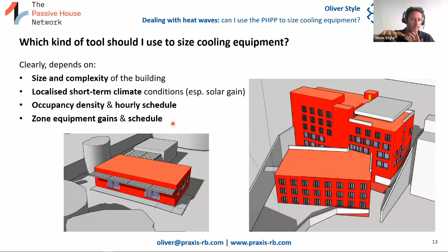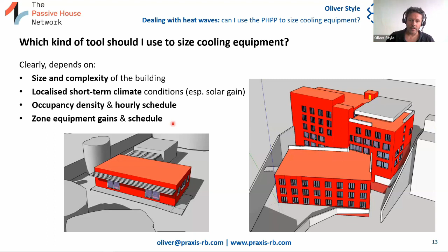And then of course, what equipment is in there, when is it on, and how much heat is it going to add to the space? Of course, in multi-residential Passive House, for example, recirculation circuits on the domestic hot water can be a real killer, because we've got this 60 degrees centigrade water recirculating around a building 24 hours a day, and that's a massive radiator heating up our building. So these are all the things we need to take into account.